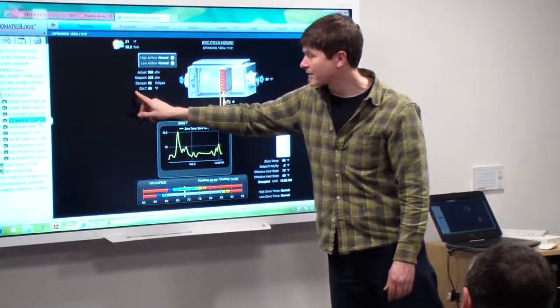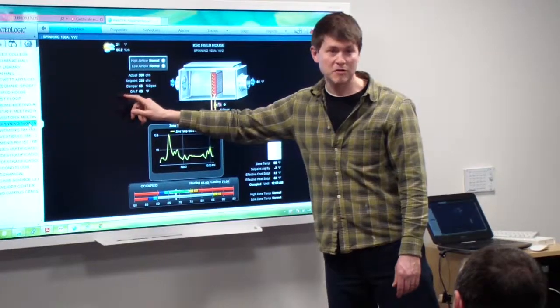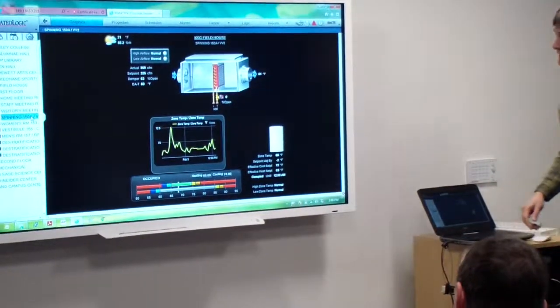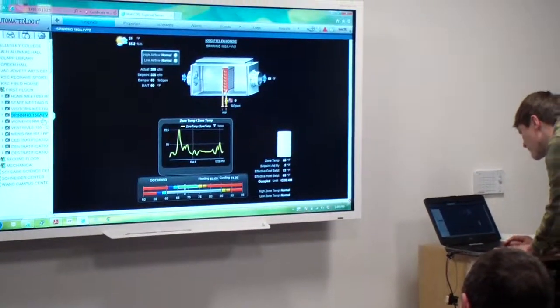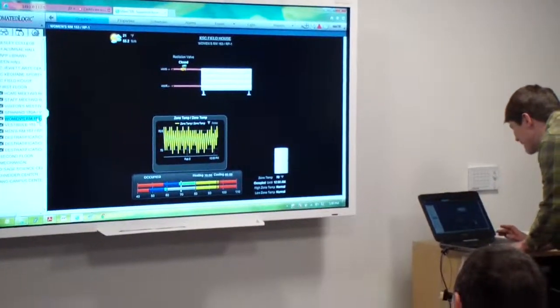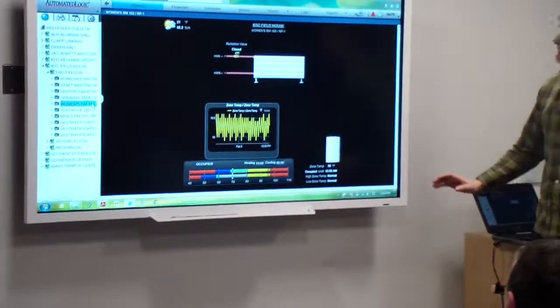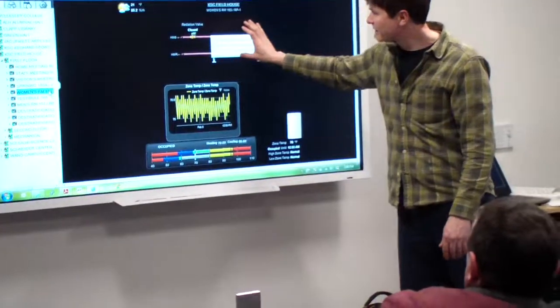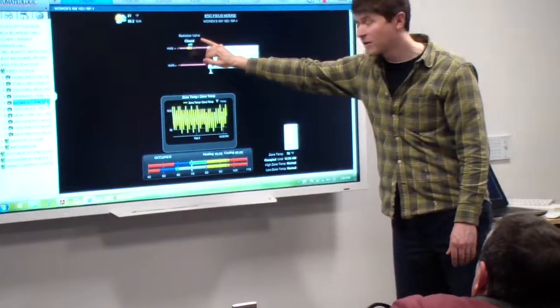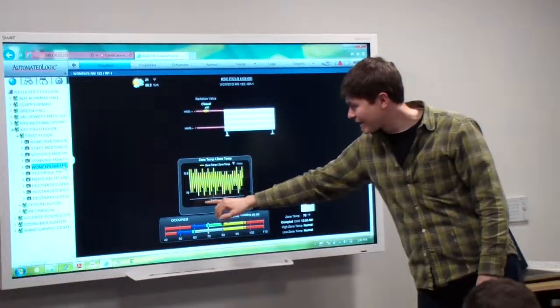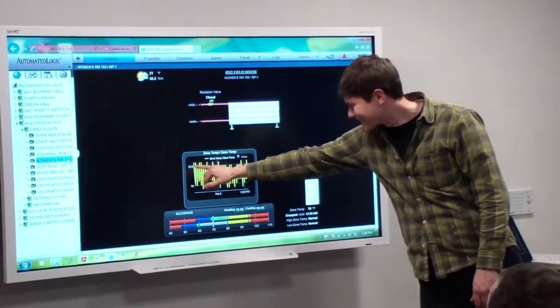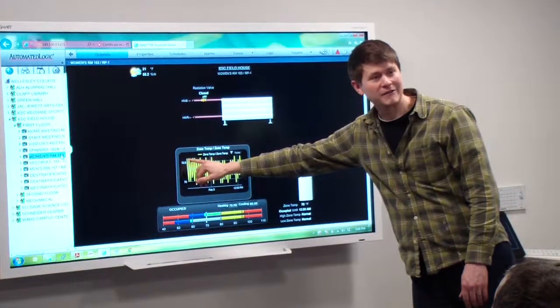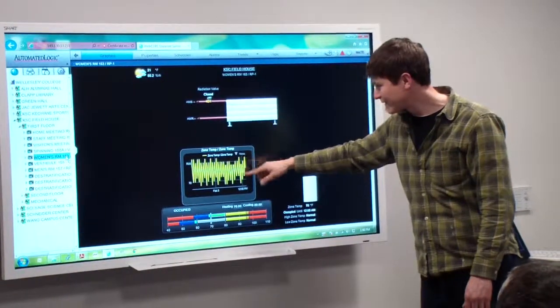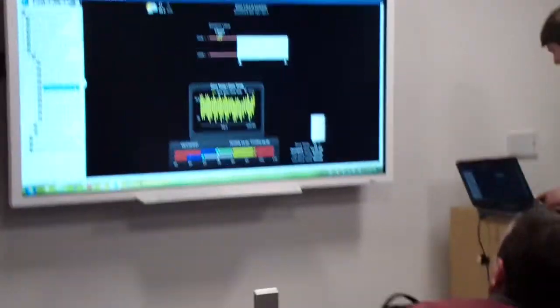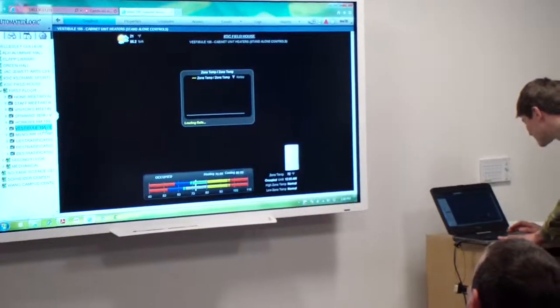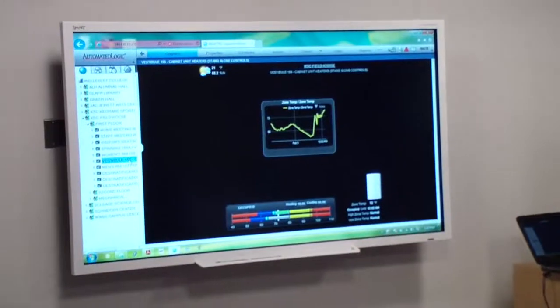We're going to alter this graphic so it spells out specifically AHU10, which is where it's getting its airflow from. Women's room, which is the women's bathroom. There's a piece of radiant that's in the ceiling, just demonstrated by this segment here, and you can see whether it's open and closed. This wild graphic here, it's showing you it's between 70, 75, 70.5 after that, so we're still maintaining, even though it looks like it's a little out of control. The vestibule section, which has a standalone cabinet unit heater.